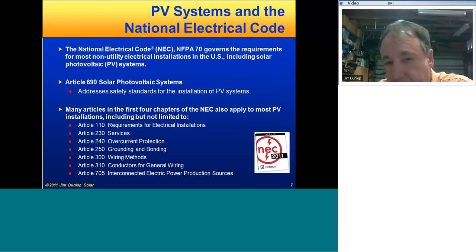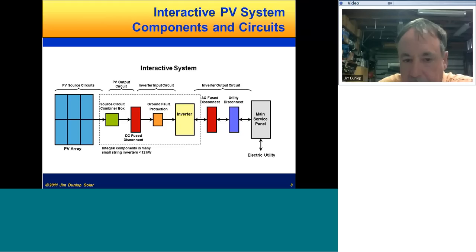Now, as they get into the rest of that standard, they talk about a lot of the British and the European IEC electrical code, basically, the International Electrical Code. And it's very similar to our electrical code, the NEC. This has different conventions for wire sizing, but most of the fundamental requirements for systems are the same for PV systems as well. That's kind of an overview of what our code covers. A lot of stuff in the first four chapters, as well as Article 705 on the interconnection stuff now. Just a diagram on some of the circuits and components that constitute the system, the definition of the various circuits and so forth in the system. We've got the PV source circuits, output circuits, inverter input circuits, inverter output circuits. These are all things that get verified and do the testing and commissioning in a system.